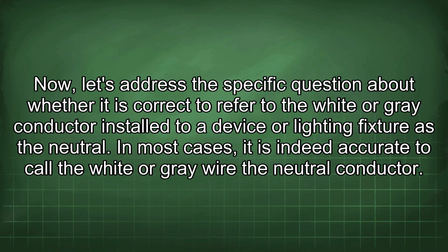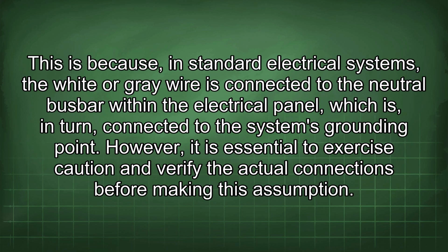Now let's address the specific question about whether it is correct to refer to the white or gray conductor installed to a device or a lighting fixture as the neutral. In most cases, it is indeed accurate to call the white or gray wire the neutral conductor. This is because, in standard electrical systems, the white or gray wire is connected to the neutral busbar within the electrical panel, which is, in turn, connected to the system's grounding point. However, it is essential to exercise caution and verify the actual connections before making this assumption.